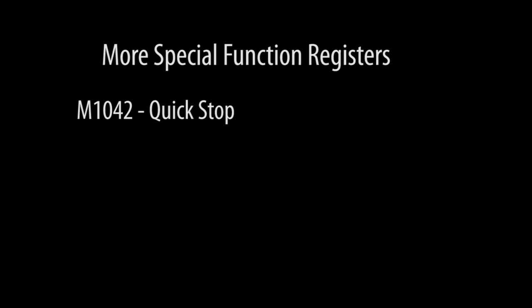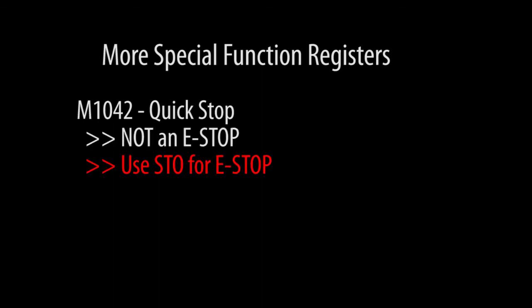So you could have one of the inputs drive this special function register and use that as a super easy way to stop the drive via ladder code. But don't think of it as an e-stop. Use the drive's STO function if you need a true e-stop.